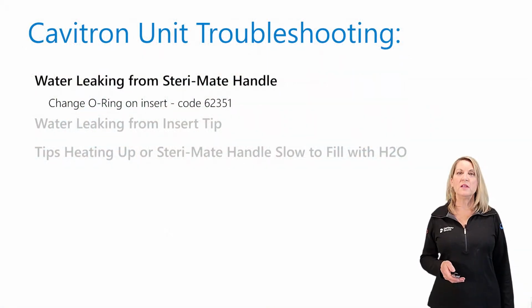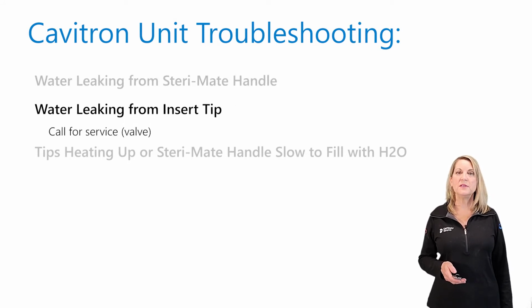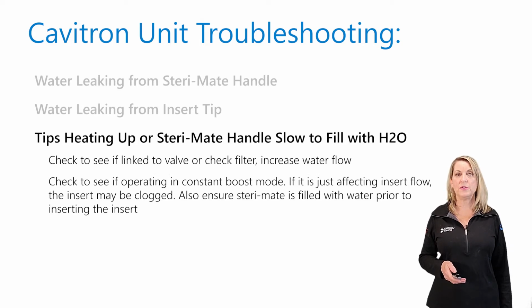If you find there is water leaking from the insert tip, you need to call your service technician, as this usually indicates a solenoid issue. If your tips are heating up or the Steri-mate handle is slow to fill with water, you first want to check the water filter to see if it is clogged. Then check to see if you have been operating your unit in a constant boost mode from the foot pedal. Also, always ensure that your Steri-mate is filled with water prior to inserting your insert. A dry Steri-mate will create hot spots and therefore potential damage.